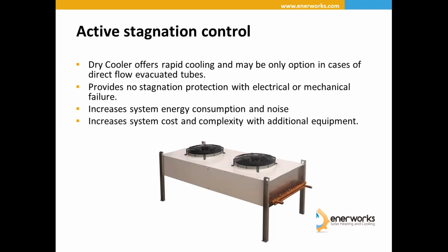So we've had simple things like an automatic valve stop working. And if you're planning for power failures, now you have to add in a backup generator. And so it ends up becoming very expensive to provide the redundancy if you're trying to use this as your primary method of overheat protection.